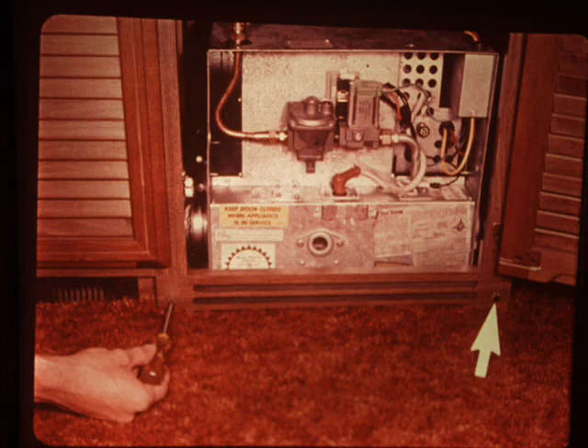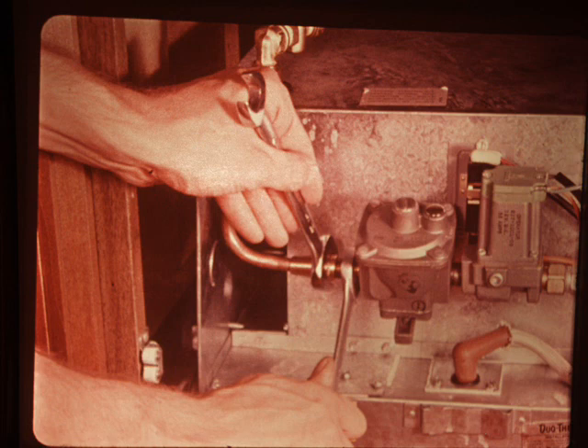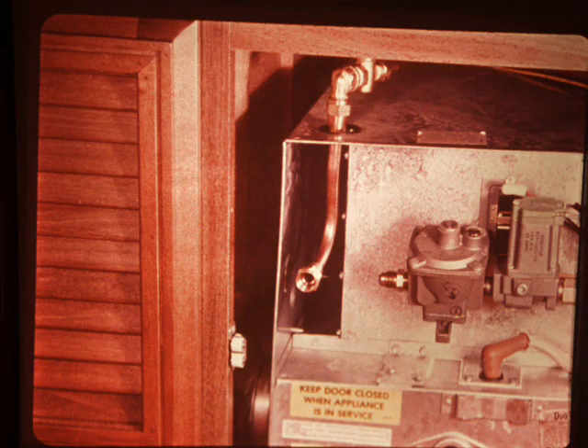To remove the combustion chamber assembly, shut off the manual gas valve at the top of the furnace and then remove the front toe board. Disconnect the gas line lower fitting from the gas valve. Then, loosen the upper fitting at the manual valve. Rotate the gas line 90 degrees so it won't interfere when you pull the combustion chamber out.